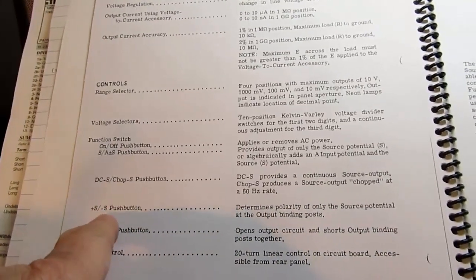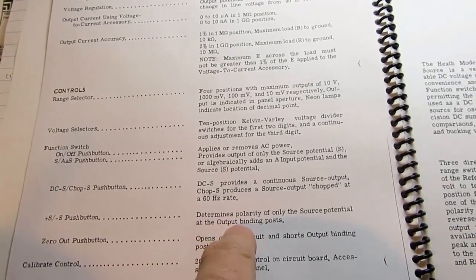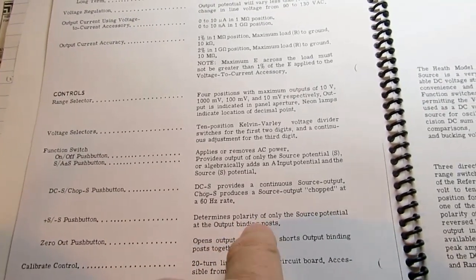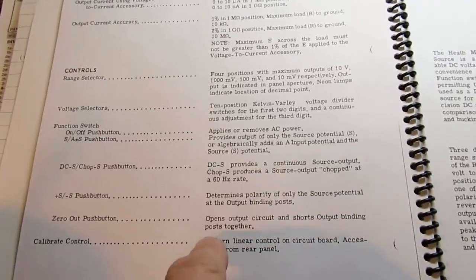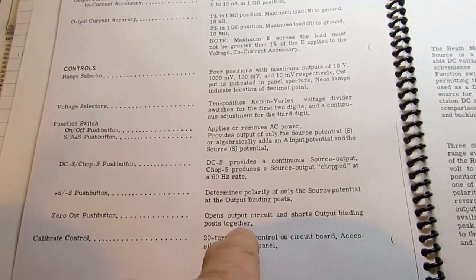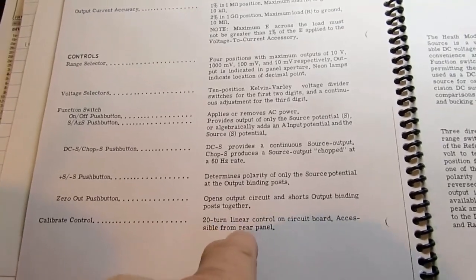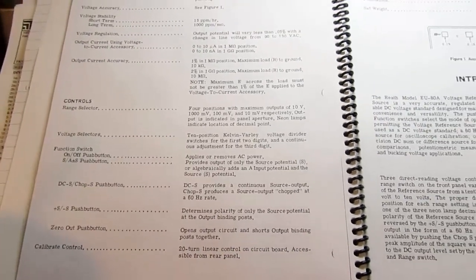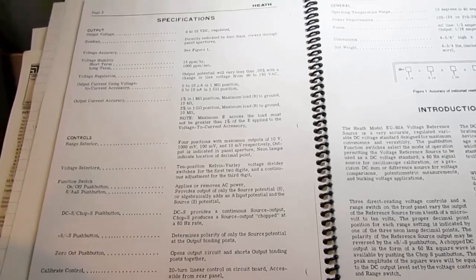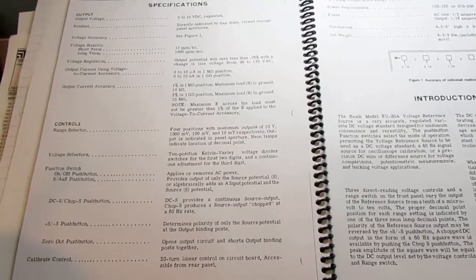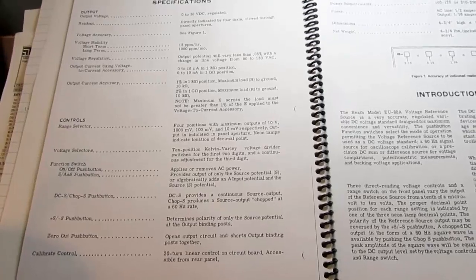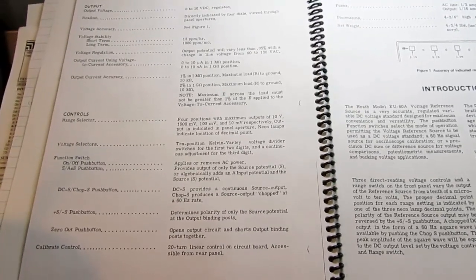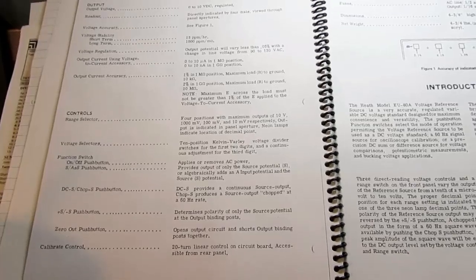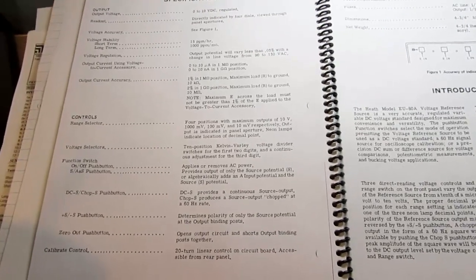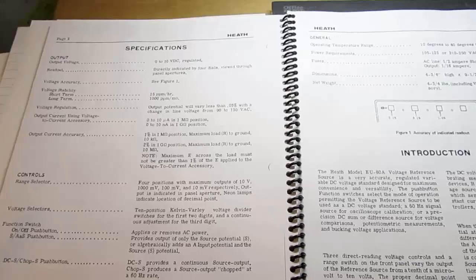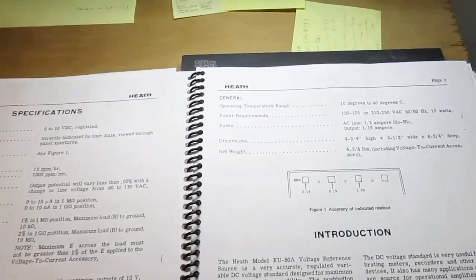There is a plus S minus S push button which allows you to change the polarity of the source potential coming out of the output binding post. There's a 0 push button to short the output leads together. And there's one calibrate control. This is a lot less fussy than the other one, which had a calibrate control for the voltage, and then you had to dial in the proper current for the Zener-regulator stage and the voltage regulator tube stage. So all very iterative and takes a lot more time. This one's much nicer in that regard.